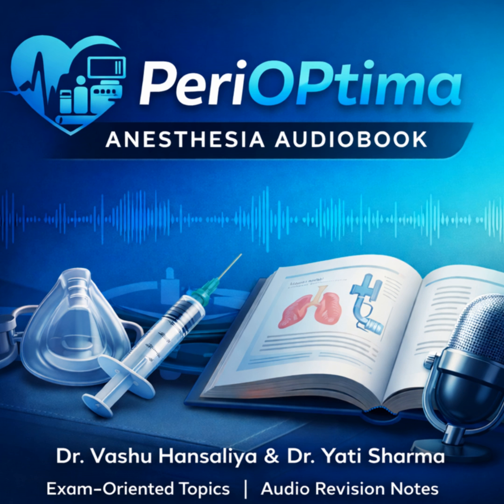No, not at all. We are talking about 2,000 pounds per square inch, or psi, for a full oxygen cylinder. That's roughly 137 bar. It is a massive amount of potential energy, which you absolutely cannot deliver to a patient. If you release that directly into a patient's lungs or even into the flowmeters, you would blow the machine apart and cause catastrophic barotrauma. The sole purpose of this system is to contain that bomb and feed it into the regulator.